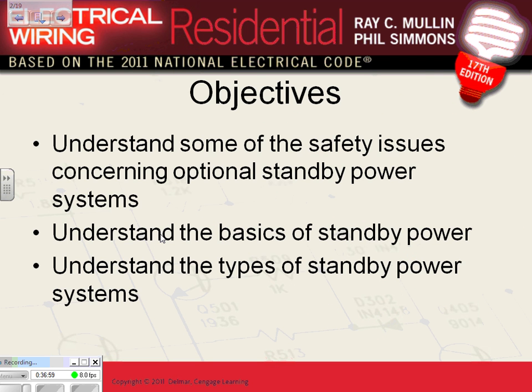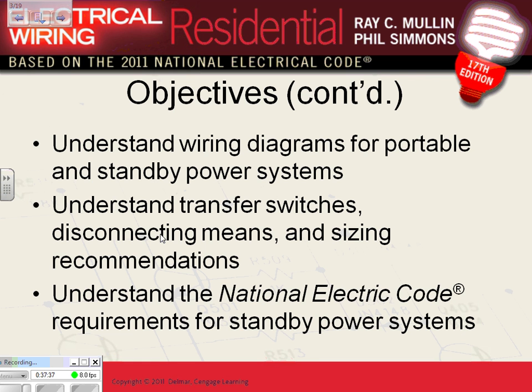Okay, standby power system. A couple of safety issues, guys, when it comes to a standby power system. I hope you understand what we're talking about: we have a grid and a service coming to my building, and I need another source of power to tie to the grid, either live or synchronous or non-synchronous, but another source of power to my building. That's what we're talking about. A couple of basic things about standby power, and the types of standby power system that you can do. The major type we're going to talk about, guys, is a motor here.